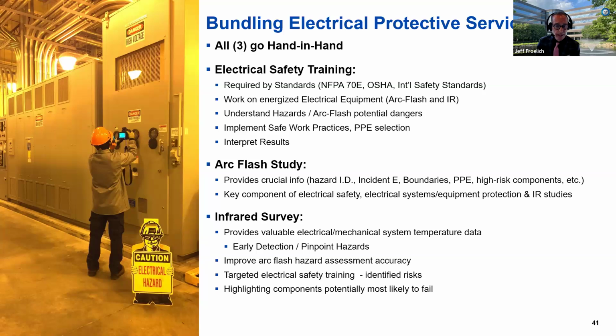It's crucial for the infrared surveys because now you know which panels are safe to open, and it provides guidance for covers to be safely removed. We talked about that earlier in the presentation. Some covers aren't going to be removed if there's too high an arc flash incident, or if the risk assessment shows it's not safe to do so. So the infrared study relies heavily on that.